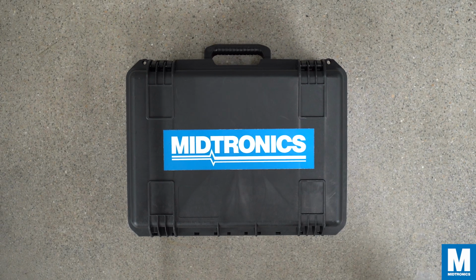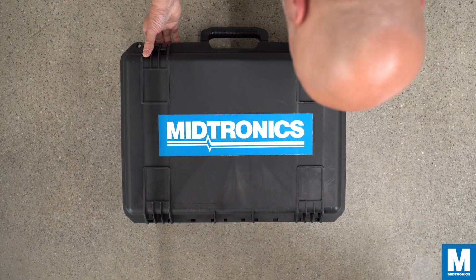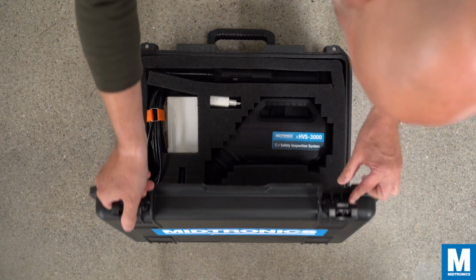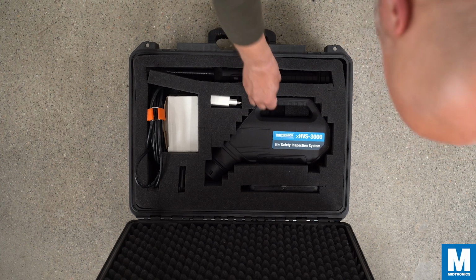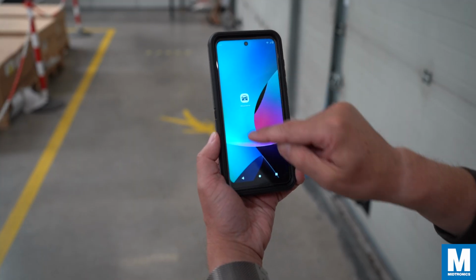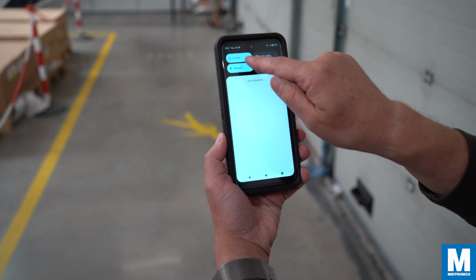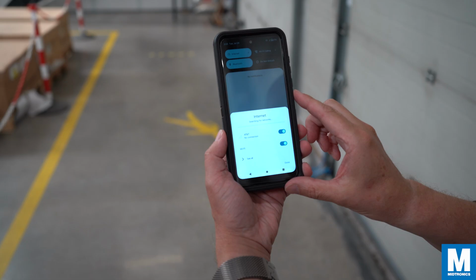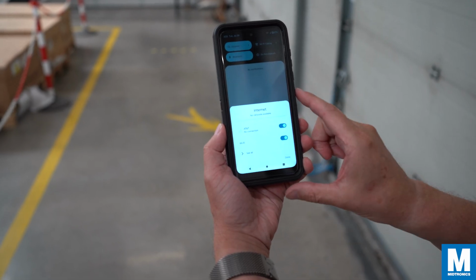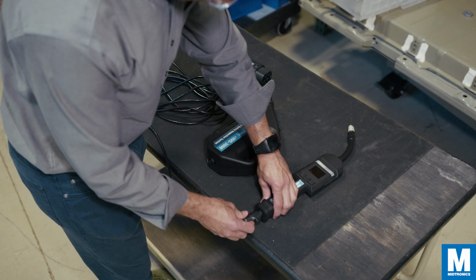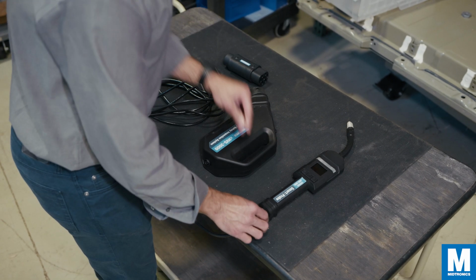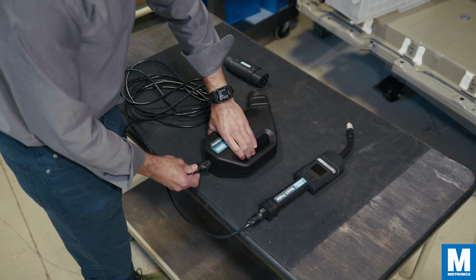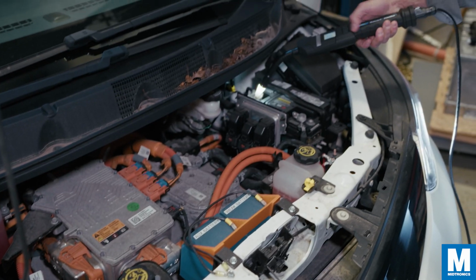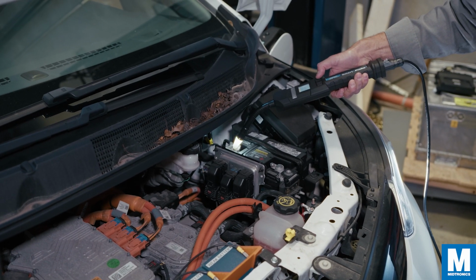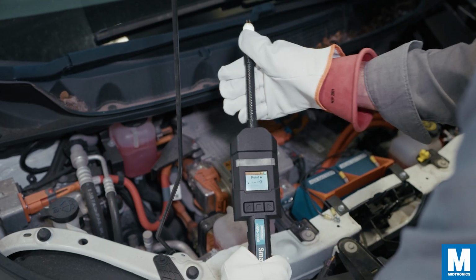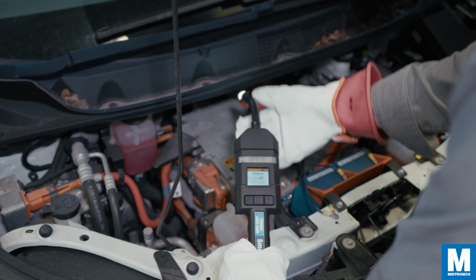To set up, remove the xHVS plug tool, the smart probe, the ground bond cable and the controller from its storage case. Turn on the controller and swipe down from the top to connect to your local network. For ease of use, ensure that Auto Connect is selected. Finally, connect the smart probe to the plug using the ground bond cable. The smart probe features a 4-wire Kelvin design for accurate measurement and a flexible neck to easily reach high voltage components.